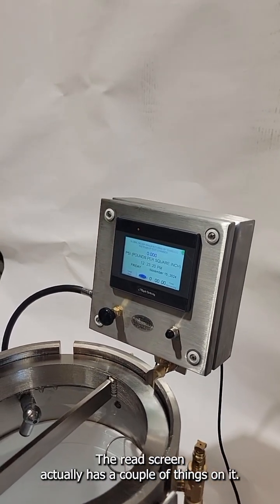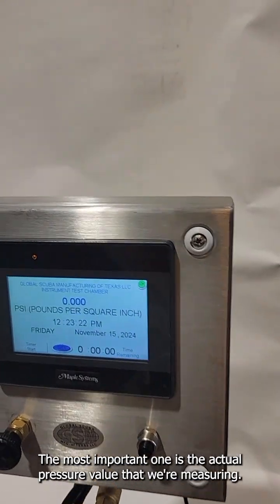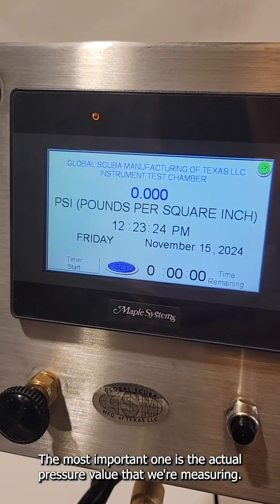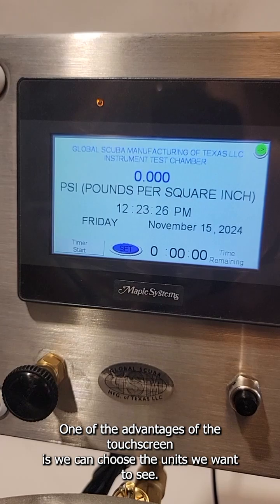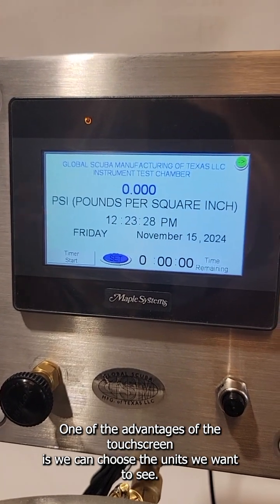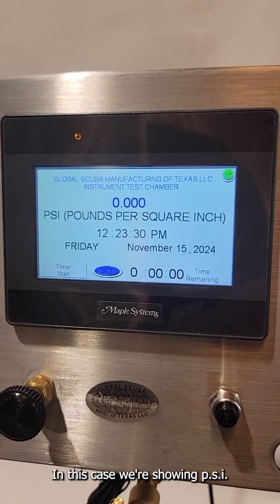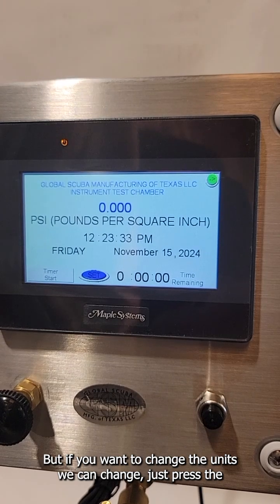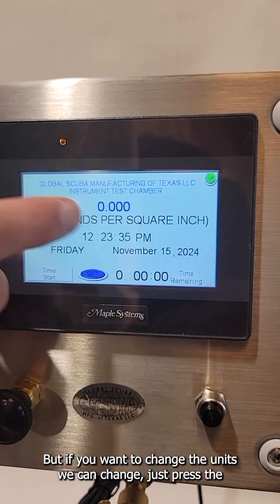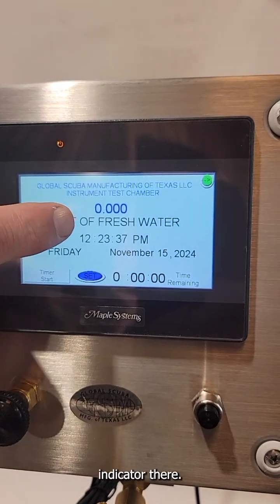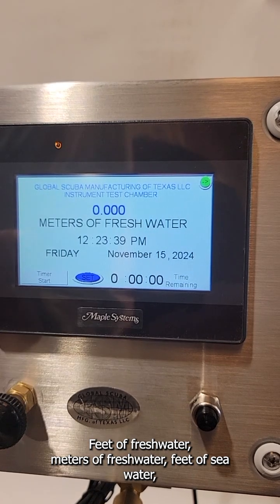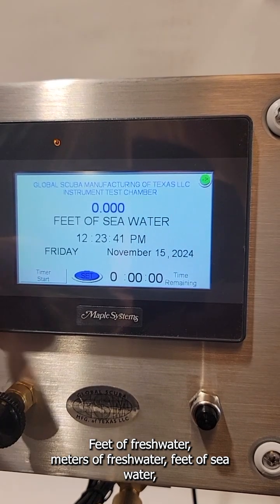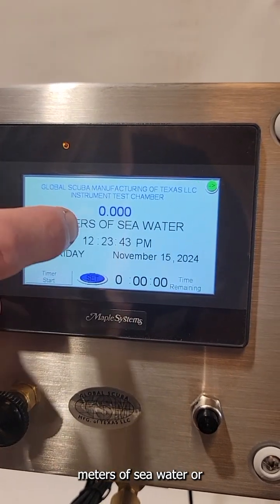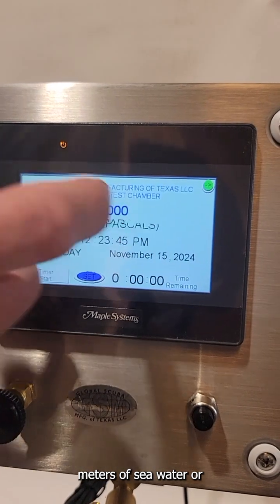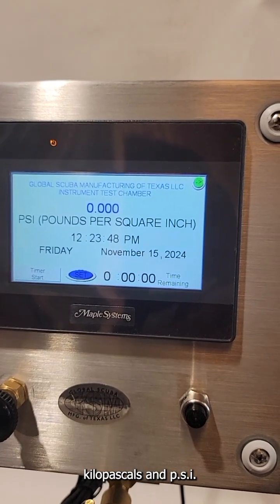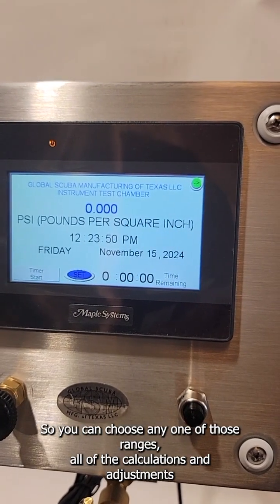The read screen actually has a couple of things on it. The most important one is the actual pressure value that we're measuring. One of the advantages of the touchscreen is we can choose the units we want to see. In this case, we're showing PSI, but if we want to change the units, we just press the indicator there: feet of fresh water, meters fresh water, feet of seawater, meters seawater, bar, kilopascals, and PSI. So you can choose any one of those ranges.